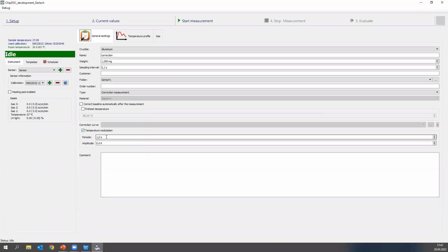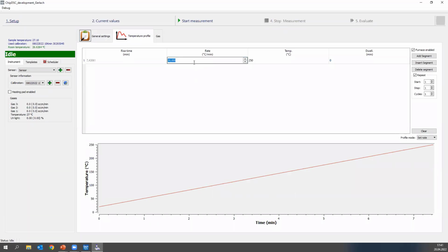What we have to set up is our temperature modulation. In many cases, I'm using a 60 second period and 1 Kelvin amplitude, and then we can choose our temperature profile. Common practice is something like 10, 5, or 15 Kelvin per minute. This depends on the temperature range. If you just want to measure until 150 degrees, I would recommend 5 Kelvin, because we need enough amplitude in our measurement. It's limited, and of course the sample also has to follow the temperature profile, so the heating rate is a bit limited.